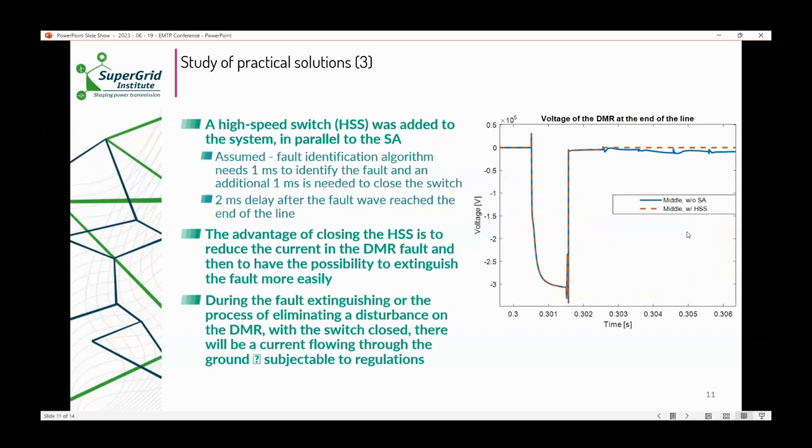We added it in parallel to have an option to extinguish the fault. Our assumption in modeling this switch was the fault identification algorithm needs one millisecond to identify the fault, an additional one millisecond to close the switch. So it means the wave arrives in the station, and after two milliseconds, the high-speed switch is closed. On the right-hand side, you can see that two milliseconds is not fast enough. This case was simulated without the surge arrestor just to show the influence and ability of a high-speed switch. It shows the high-speed switch cannot prevent the flashover, but when it closes, the voltage goes to zero. So it can help us extinguish the fault. During the fault extinguishing or the process of eliminating a disturbance of the DMR, with the switch closed, there will be a current flowing to the ground. This is subjectable to regulations depending on the country and region.